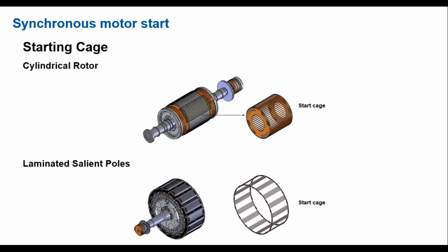Right, I mentioned that the synchronous motor designs, the two that we've just discussed, unless you use a pony motor or some kind of an external starting method, are unable to self-start. And so in order to self-start them, you need to incorporate a squirrel cage into the field winding, into the excitation winding, to allow induction startup like a normal squirrel cage induction motor would start. And this slide just shows the construction of the starting cage that is essentially built in and incorporated in the rotor design.